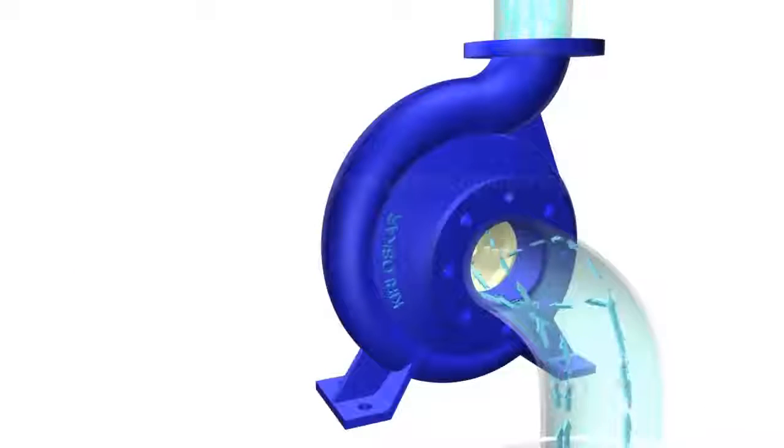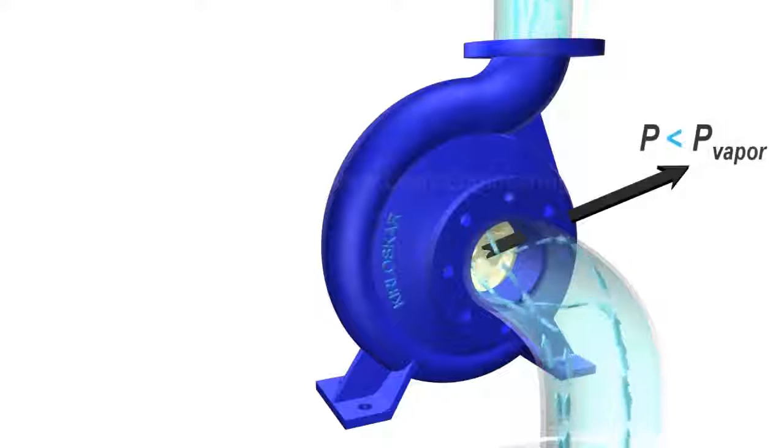If pressure at suction side of impeller goes below vapor pressure of water a dangerous phenomenon could happen. Water will start to boil forming vapor bubbles and spoil impeller materials over time.